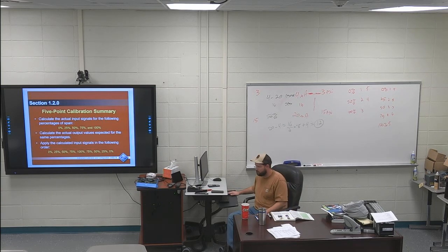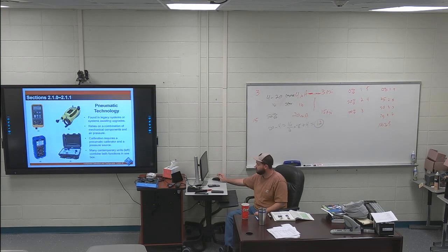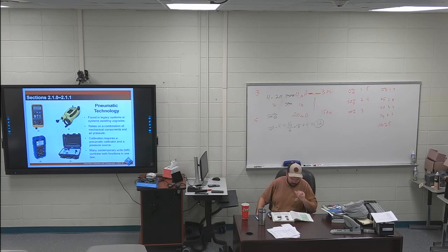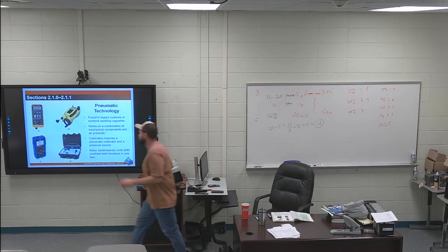All right, section 2. Pneumatic and analog calibration. So you're going to have different types of instruments that can do this. You'll have crystal gauges, a Fluke gauge. They have that GE Druck that will output a pressure with that little pump. Some of them have a pump built in. I think that crystal gauge has a pump built into it, maybe even the Fluke one does too. You can see the button that says pump. But that will literally pump up a piece of instrumentation up to a certain pressure. If I had a valve that I had to calibrate to 3 to 15 psi, and I didn't have an air source, I could take a meter like that, or you can have, let me go grab it.